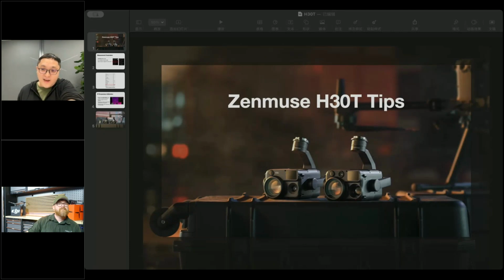Okay, so if you click the IR temperature calibration on the list, it will take you through a process, and if you follow the process, you can finish the calibration. But being allowed to do this doesn't mean you have to do it every month, every week, something like that. I asked our R&D team, they said most users probably never have to use this feature unless, for example, you look at some overheated object, like accidentally looking at the sun for a long time, and maybe the accuracy is a little bit affected. If something like this happens, you can do this calibration.